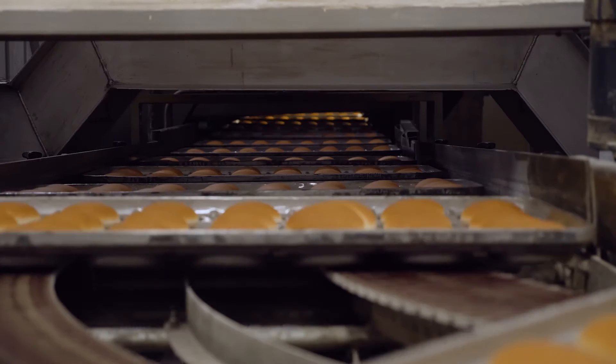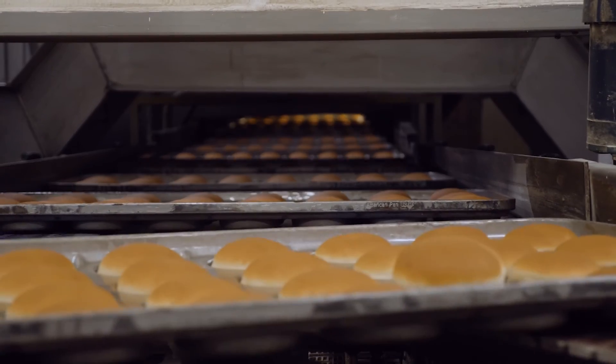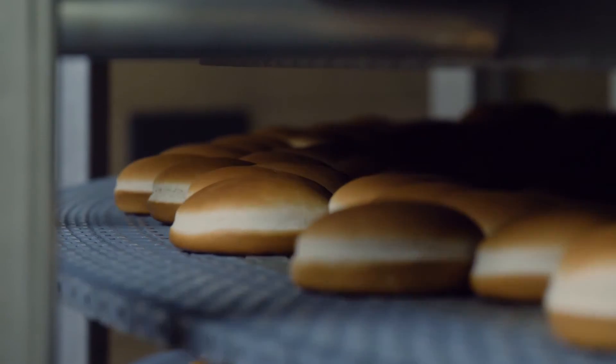If you can't get flour into the bakery, you can go to the maintenance screen and instead of spending time looking inside the bakery, it shows you a flour blower outside has kicked out. In a nutshell it cut troubleshooting down by probably 50%. We still do experience downtime but not to where we were before.